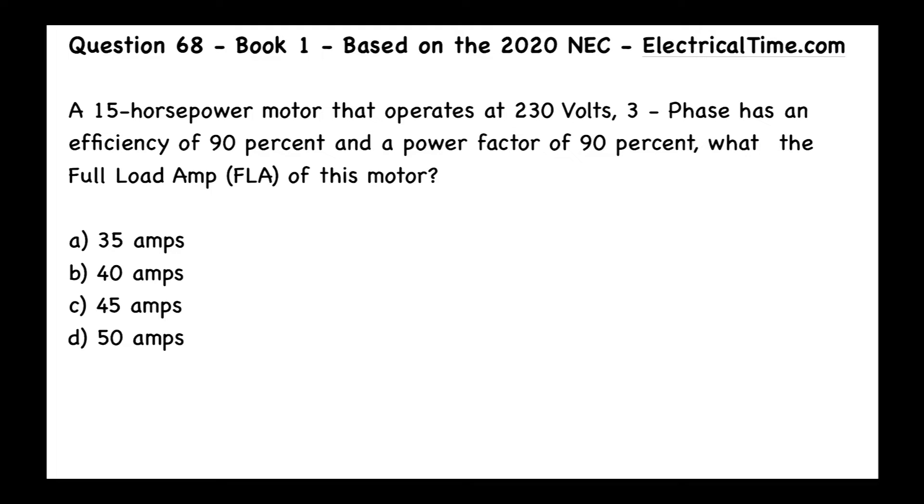This is question number 68 from book number one based on the 2020 NEC, and this is electricaltime.com. A 15 horsepower motor that operates at 230 volts three-phase has an efficiency of 90% and a power factor of 90%. What are the full load amps, or FLA, of this motor?